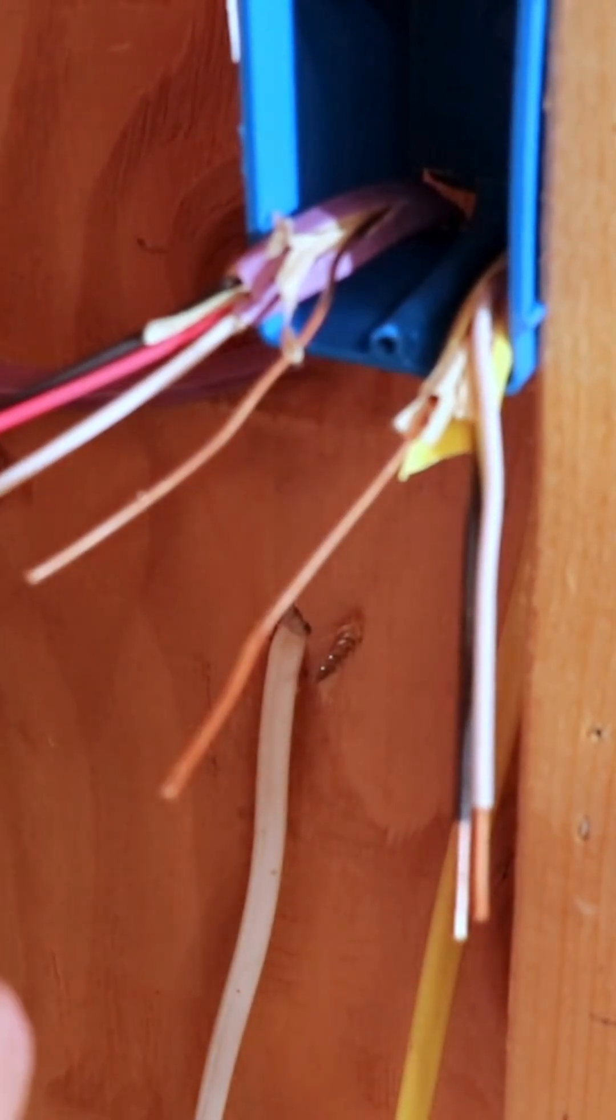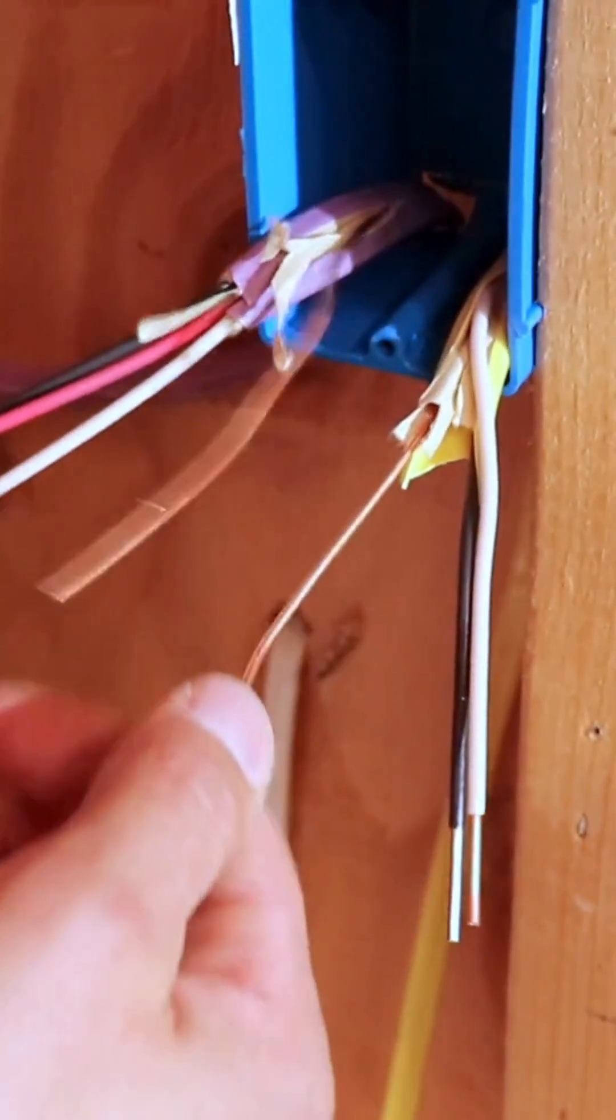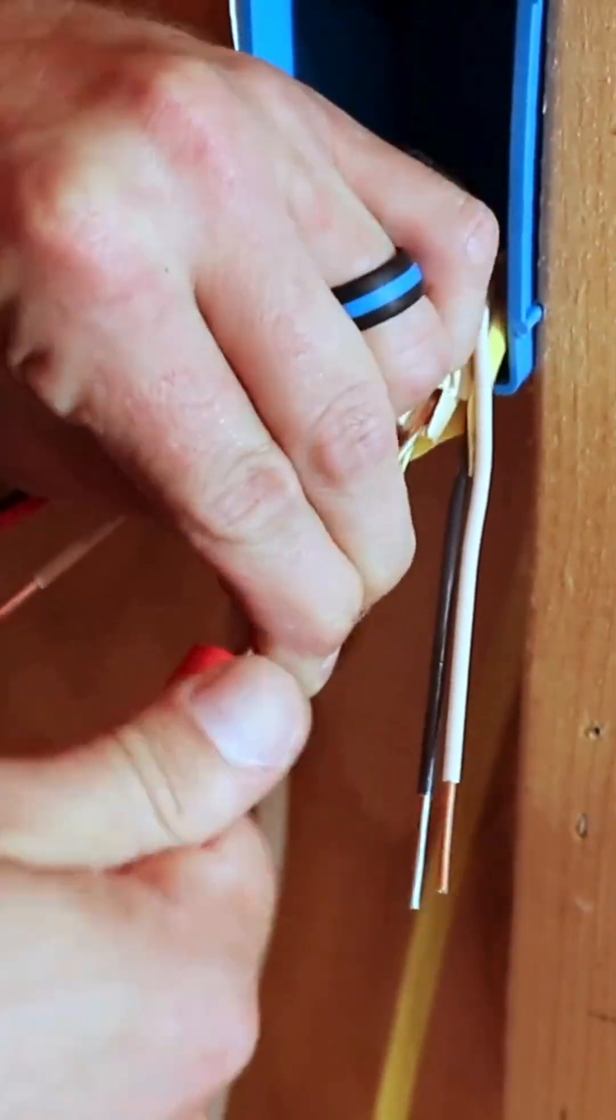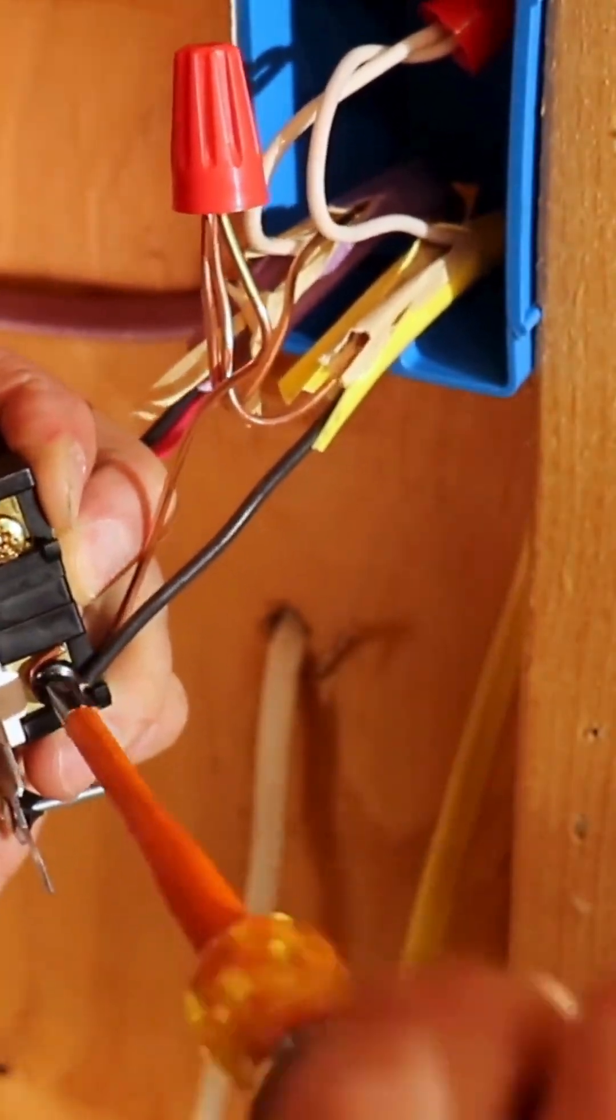To wire this switch, we first need to wire nut the grounds together and use a pigtail to connect the ground wire to the switch. Next, we can wire nut our neutrals together, then we can connect our hot wire from the 12-2 to the common terminal, which is the black terminal.